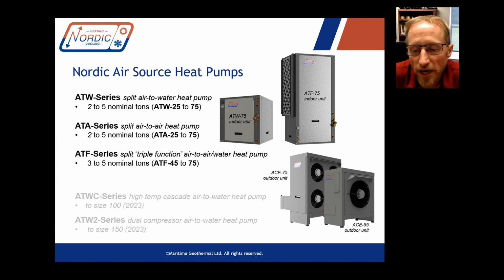So it'll be able to dial back a lot further. You could put it in place, like you could put an ATW 150 where you would have put an ATW 75 previously, but the ATW 150 would spend most of its time running with only one compressor energized. Then on a cold day, where instead of using backup heat to make up the capacity difference due to it being harder to extract heat from the outdoor air, you could use this ATW 150, which would have the capacity to dial up in case you needed more capacity on a cold day.